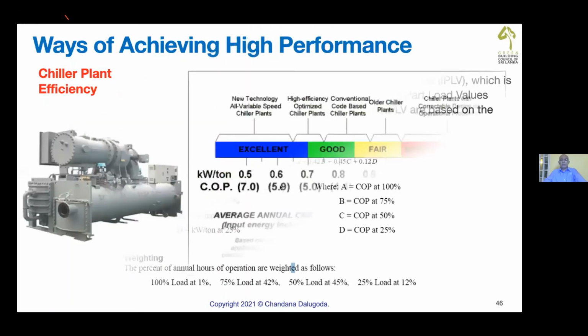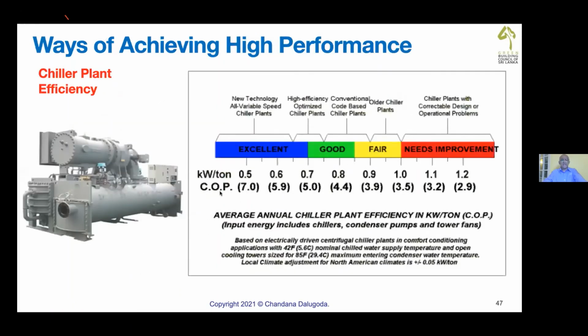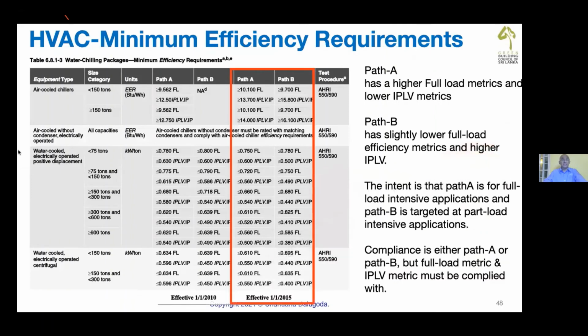This is how the efficiencies of chillers and air conditioning equipment are given. 0.7, 0.6, excellent, 0.5. What you can see here is ASHRAE 90.1 compliance for an air-cooled chiller and water-cooled chiller, 75 ton and below. What is your required full load efficiency? 0.75 kilowatt per ton. Part load efficiency 0.78, something like that. Part load efficiency is 0.6, sorry. 0.75 and 0.6, that is full load and part load.